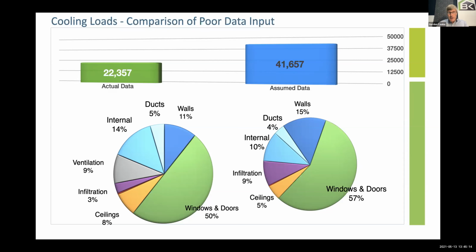Heat gain is double. So what's the appropriate size on that house? Well, 22,000 BTUs. You could actually go 1.5 tons. 1.5 is a little small. Go to 2 ton. And if you said, yeah, but I really want to be safe, I want to go to 2.5 ton. I'm actually okay with that. 2.5 ton is fine. Oversize a little bit. Just don't put in a 3 or 3.5, or in this case, this is showing 3.5 tons on the right-hand side.